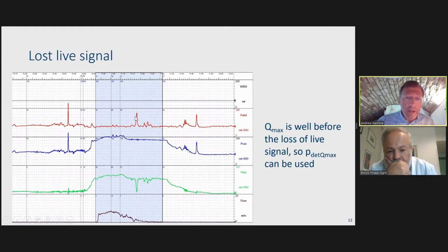And when they cough during that end of voiding, here's the cough on the abdominal line, but there's nothing on the vesical, it's lost. So the detrusor's got this big negative spike, which is an indication of a problem. Later on, it actually comes back. Your cough is good. The bladder's pretty well empty by then. But in the middle, we can't trust that signal. It's got a loss of these quality indicators. However, in this case, if the point you're interested in is the maximum flow, and you want to see if this patient is obstructed by looking at detrusor pressure and maximum flow, the question is, is the quality still okay at that point?